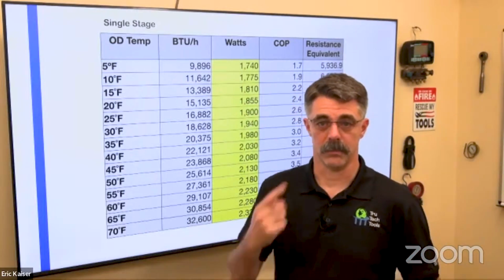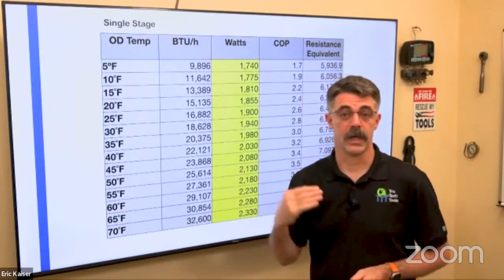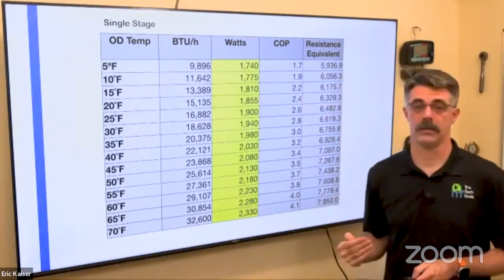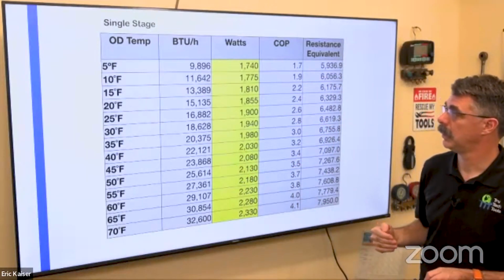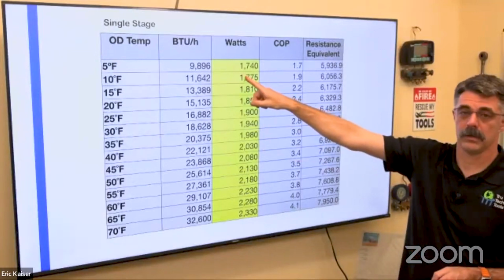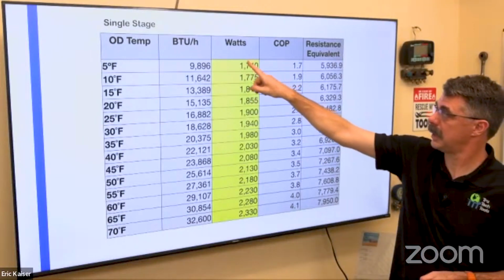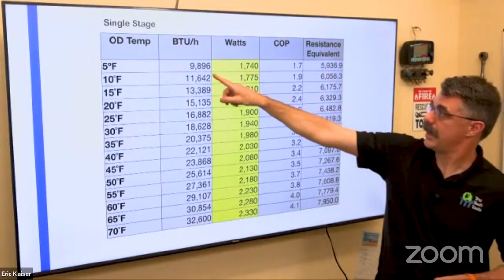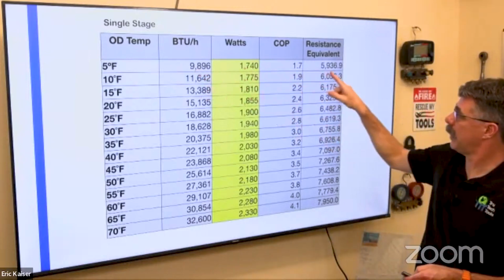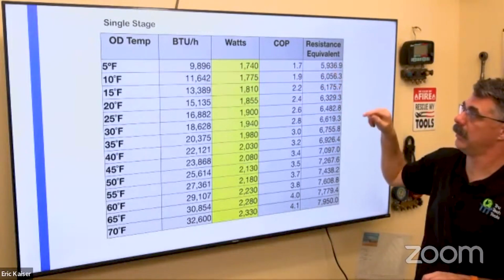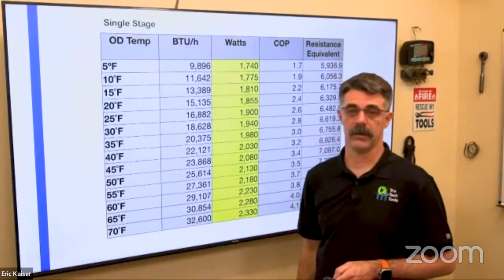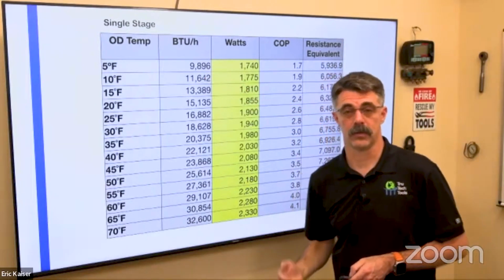This is why we use heat pumps, right? Because we can move heat for less energy being used. And even down at 5 degrees, I can still get 9,800 out of it, whereas if I was running electric heat, I'd only be getting 5,900. So there's still an advantage there to run the heat pump.